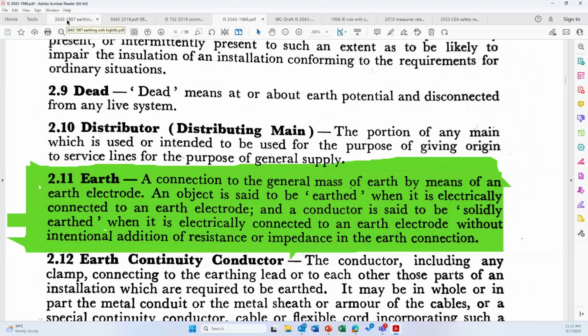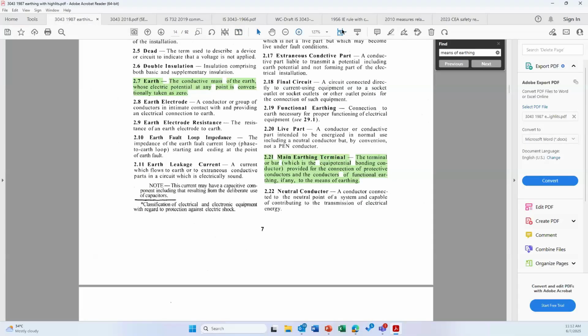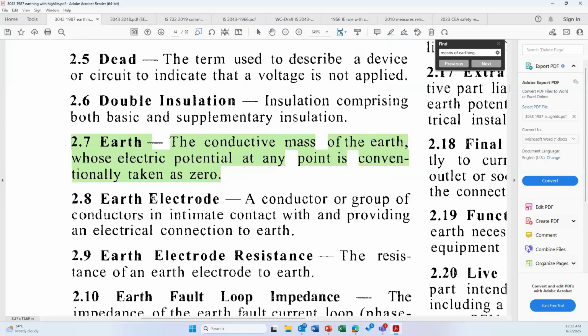When it comes to 1987, the second edition of IS 3043, the definition was modified and redefined. You can see here the green highlighted portion: earth, the conductive mass of earth whose electric potential at any point is conventionally taken as zero. So this was a different type of definition. In the previous one, it was told that you make a connection to the earth electrode in the soil. As a result, the energy immediately dissipated to the soil and you become safe. Whereas in 1987, it was redefined as the conductive mass of earth whose electric potential at any point is conventionally taken as zero. Please note, conventionally taken as zero is very important now.